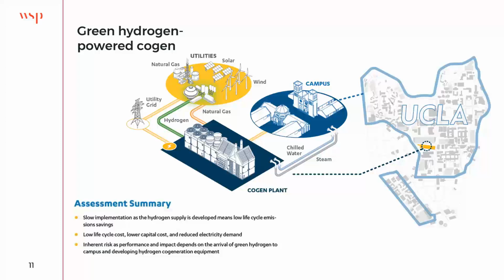We would be converting the cogeneration plant that's running on natural gas right now to a hydrogen cogeneration plant, burning hydrogen in a new hydrogen boiler and new hydrogen turbines to produce power, steam, and chilled water. The advantage is that you can maintain a lot of the cogen plant. It's kind of a like-for-like replacement to incorporate hydrogen. You still have that islandability, and you don't have to replace the steam network, which can stay in place.